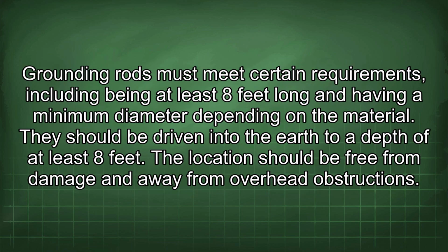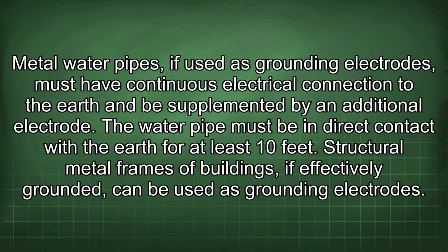Grounding rods must meet certain requirements, including being at least 8 feet long and having a minimum diameter depending on the material. They should be driven into the earth to a depth of at least 8 feet. The location should be free from damage and away from overhead obstructions. Metal water pipes, if used as grounding electrodes, must have continuous electrical connection to the earth and be supplemented by an additional electrode. The water pipe must be in direct contact with the earth for at least 10 feet.